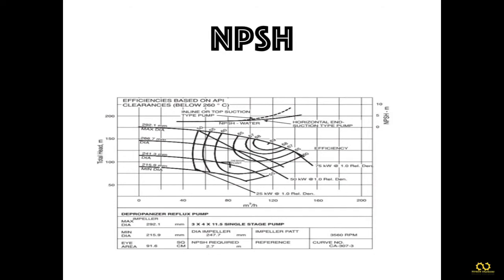I'd like to tell you briefly about this pump performance curve. On the vertical axis you can find the total head required in meters. On the horizontal axis you see the flow rate for each parameter with respect to impeller diameter. Here you can find 215.9 dia and 241.3 dia. This is the basic requirement for engineers to identify or select the diameter. You can also find the rated efficiency for different parameters.